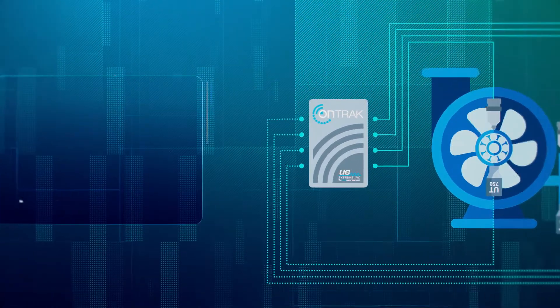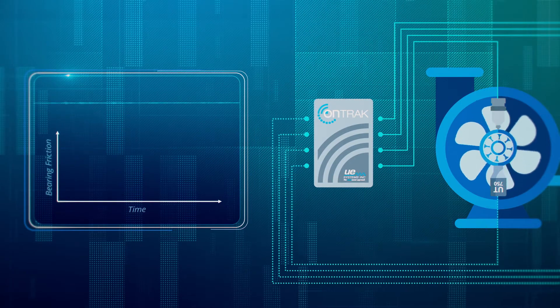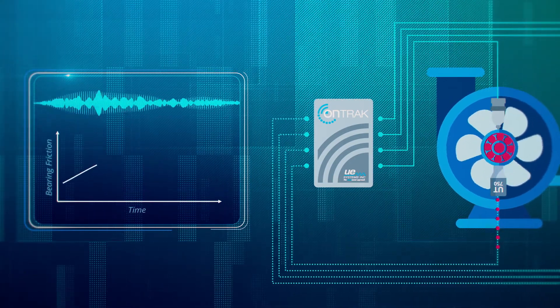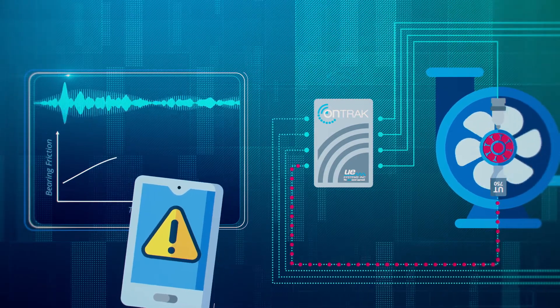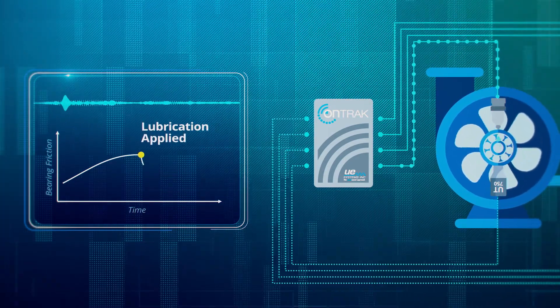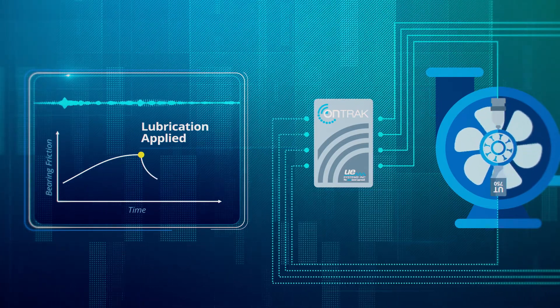By continuously monitoring the friction in bearings using ultrasound, the OnTrak SmartLoop system monitors the lubrication needs and health of bearings 24/7, notifying you the minute grease is required, and dispensing the amount of grease needed to restore the bearing friction back to the optimal level.